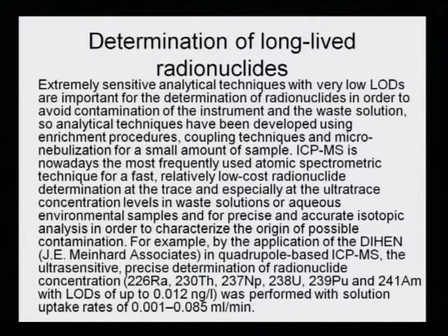disposed. And so, a very small amount of sample should be taken, and by the method of enrichment procedure coupled with a technique which can do micro nebulization, very small amount is going into the spray chamber of the ICP. That is the kind of adjustment, so that only small amounts of samples are even taken into the machine.